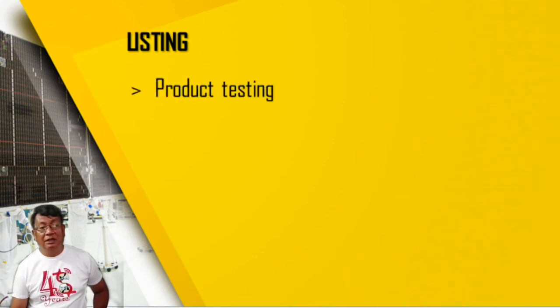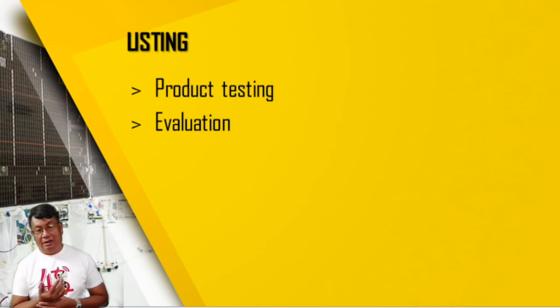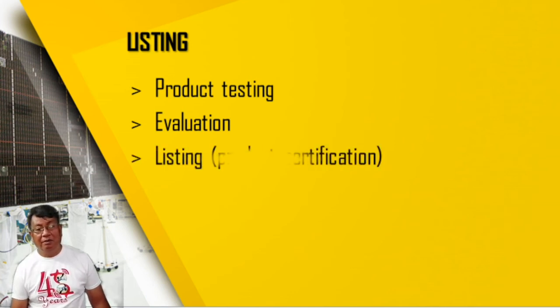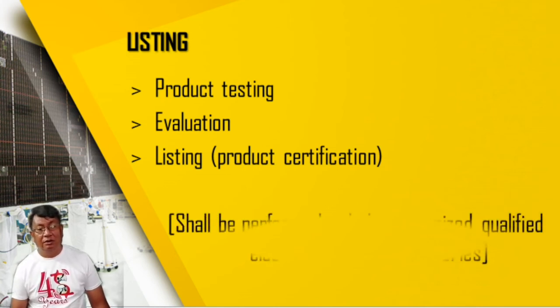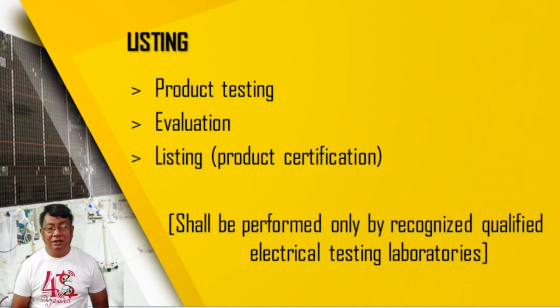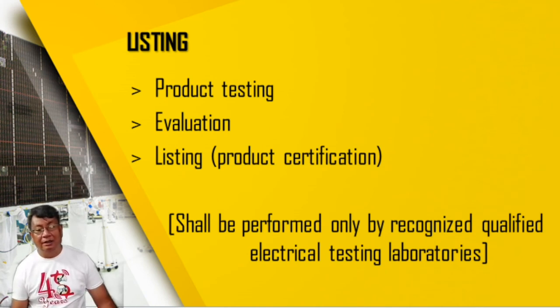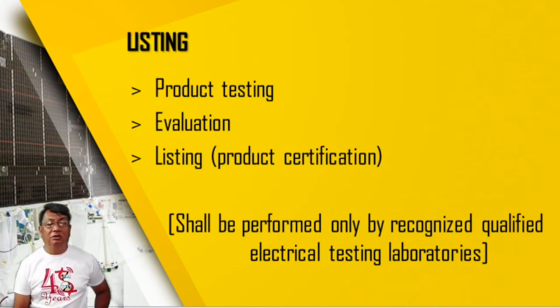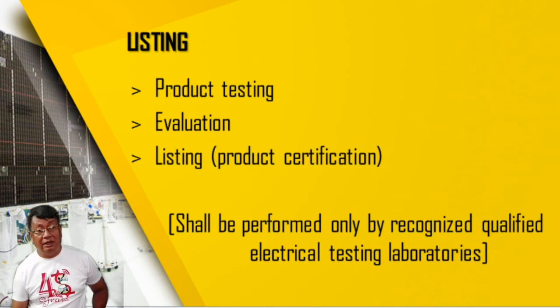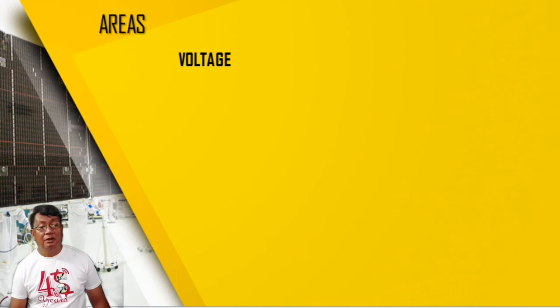So talking about listing, product testing. So you must provide product testing, especially if it is a machine. Then evaluation also, the pre-evaluation of the performance, and also the listing, product certification. Okay. This listing shall be performed only by recognized qualified electrical testing laboratories. Or, for example, the distribution utilities, they have their own testing materials for transformers and other equipment. So we have these areas.